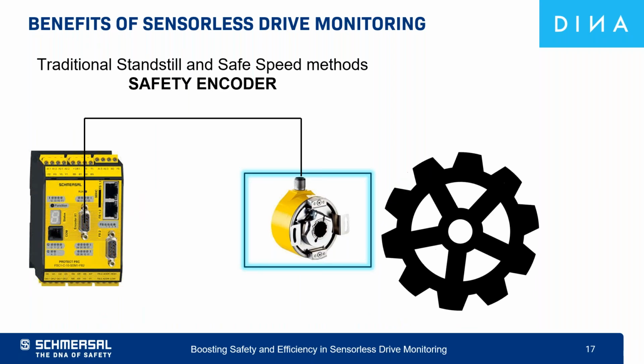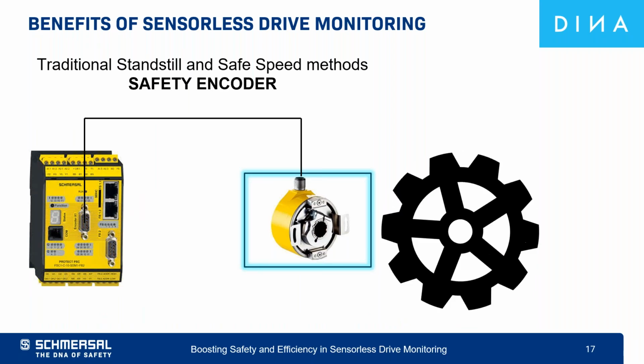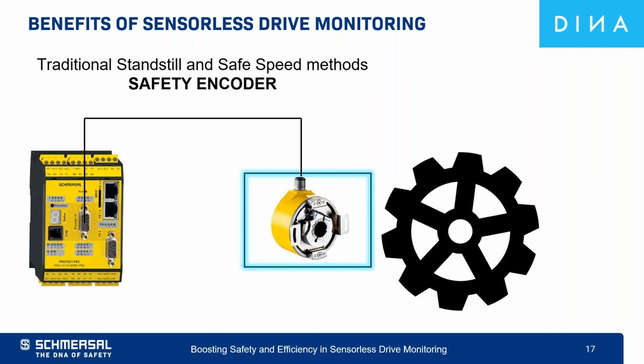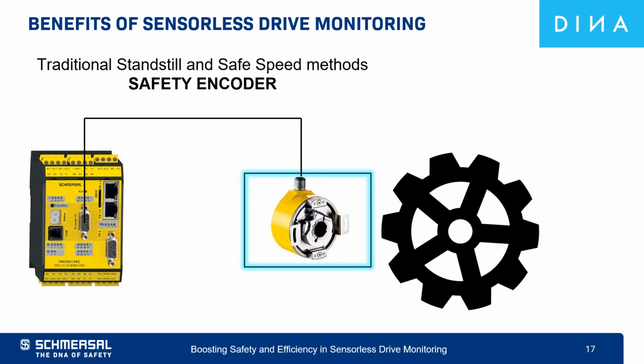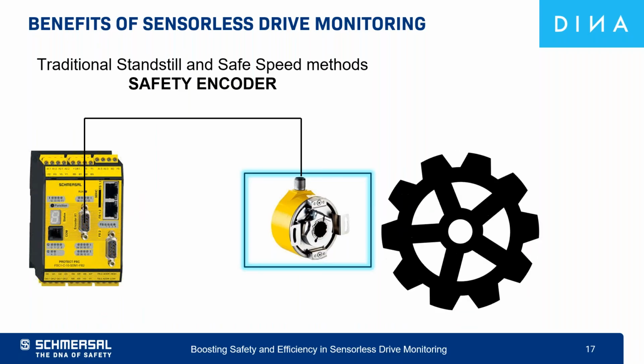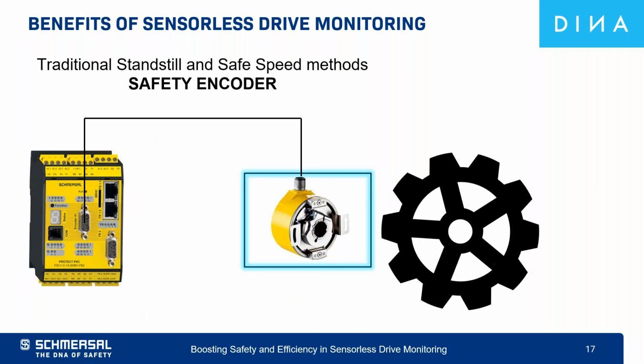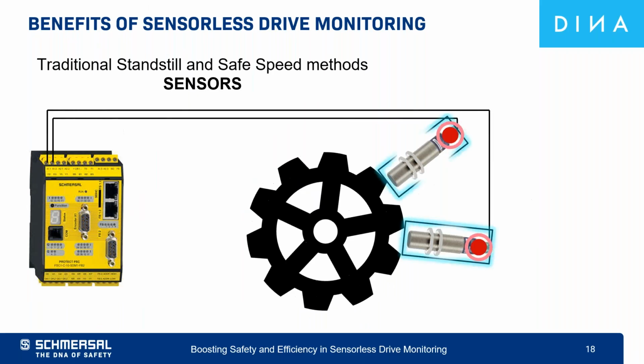Encoders can also be damaged quite easily in industrial environments. Things like moisture, cleaners, or even accidental damage from somebody working in the vicinity are things that we see as damage. Safety encoders still require being monitored by a safety PLC or a safety monitoring relay.